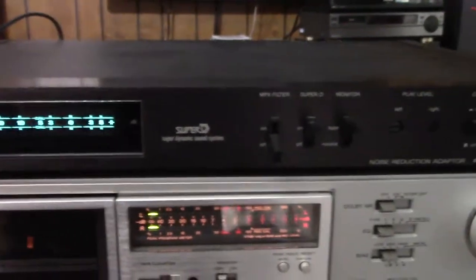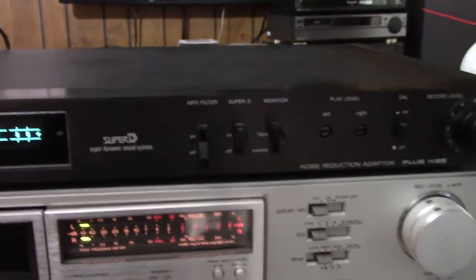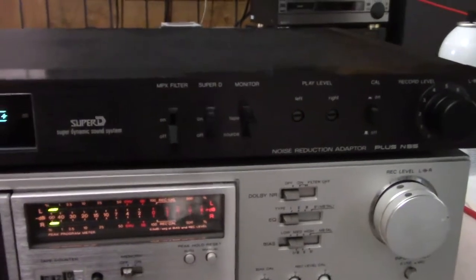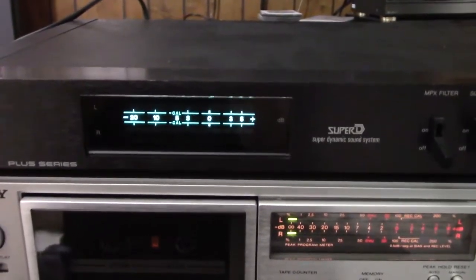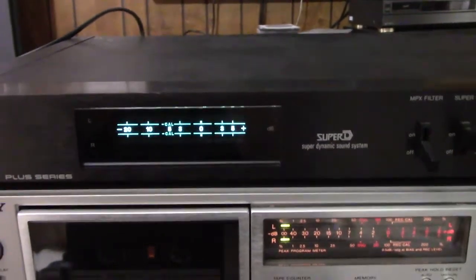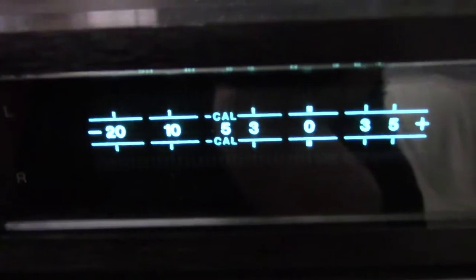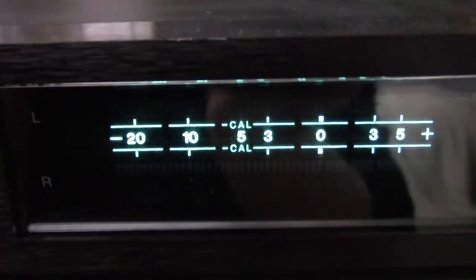Now the Super D does require calibration. It's unlike the DBX, where the DBX doesn't really require calibration, it just needs level matching. But this one needs calibration, and you see there's a little cal mark on the display there where you're supposed to match up.